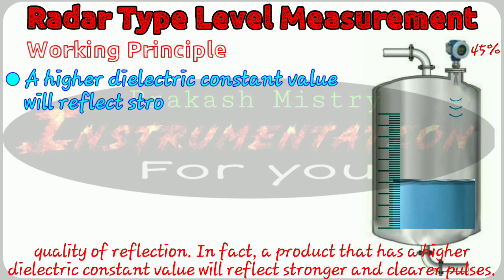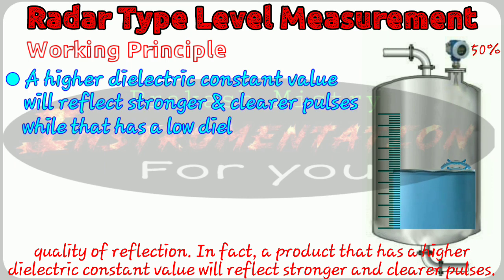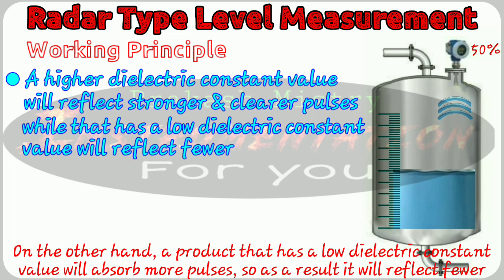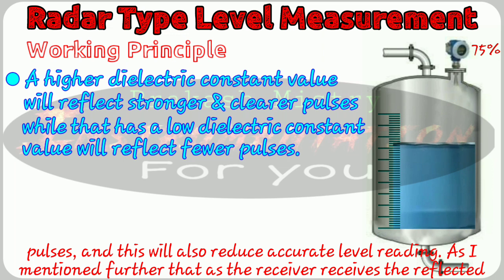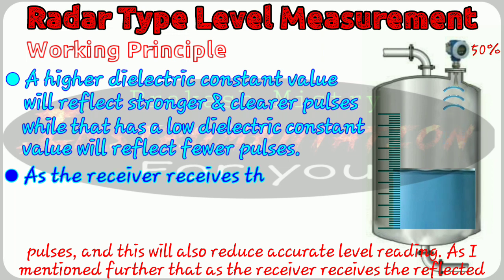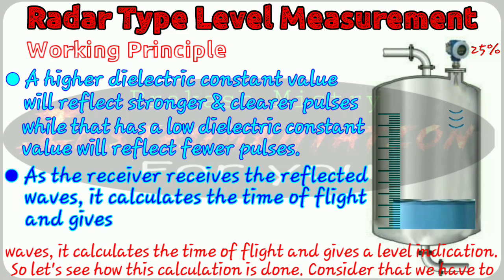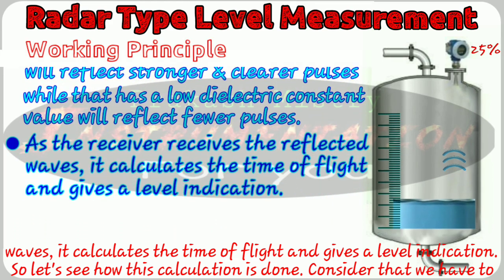A product that has a higher dielectric constant value will reflect stronger and clearer pulses. On the other hand, a product that has a low dielectric constant value will absorb more pulses. As a result, it will reflect fewer pulses and this will also reduce accurate level reading. As the receiver receives the reflected waves, it calculates the time of flight and gives the level indication.